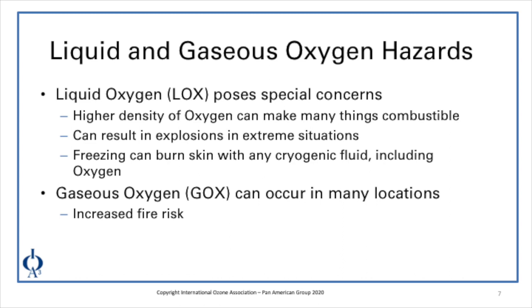For gaseous oxygen, it can occur in many locations throughout your ozone facility. The conversion of oxygen to ozone only converts approximately 10% by weight to ozone, so the remaining 90% in that gas stream will be oxygen. Even on our ozone piping throughout the facilities, we still have oxygen safety concerns present. The primary concern with gaseous oxygen is, of course, that increased fire risk.